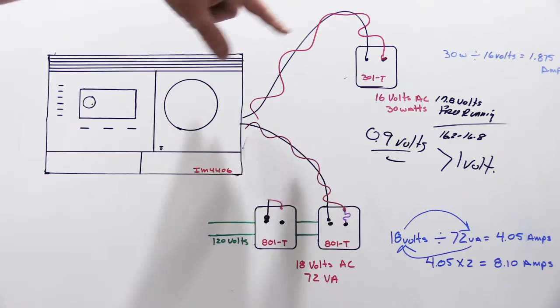And since the 301T doesn't have a fuse in it, it has a thermal limiter. When it reaches the maximum temperature that the thermal limiter is designed to operate under, it's going to open and the transformer is going to shut off. So the safety device will work. So what I'm going to show you next is what we have to do this with. This is something that I use when I go on service calls, and what we're going to do to help the fella in New Jersey.